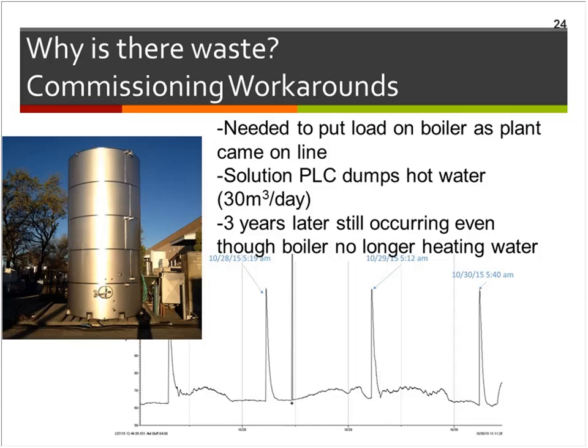Three years later, when we went into the factory, we found this practice was still occurring. The boiler was no longer even heating the hot water in the tank. So essentially, the program running the boiler room was dumping 30 cubic meters of water with no impact on the boiler, or not the desired impact. This is how a factory is first commissioned — very often, some of the most wasteful scenarios arise because it was commissioned incorrectly, or because things changed once it was up and running.